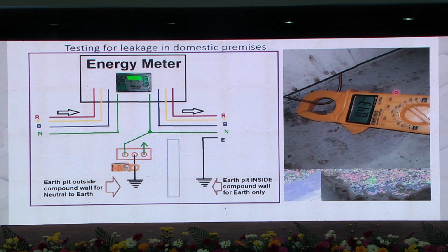Okay. This is a meter that we have connected to show what will be the condition before switching off and after switching off the supply to our home. Even after switching off, the same current is leaking through. It is not the current leaking from the consumer premises. It is the leakage current from the adjacent premises because of the earth electrode. Because of this earth electrode, it is going towards the source.